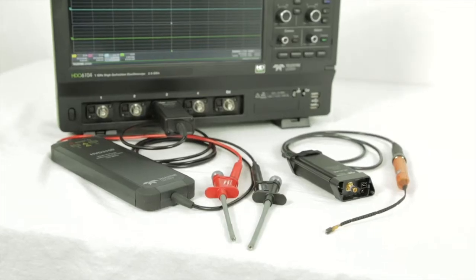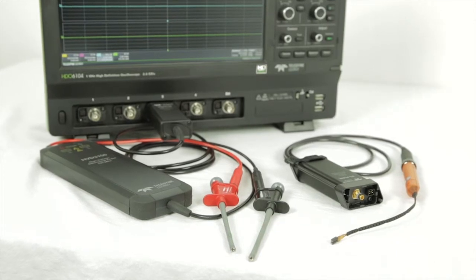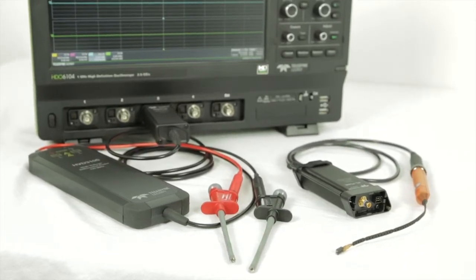The differential probe measures the difference between two signals when there is no ground reference. There are both high voltage differential probes for floating measurements, and high bandwidth differential probes for serial data stream measurements.